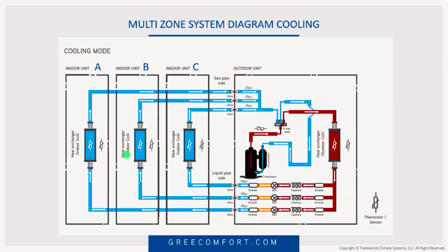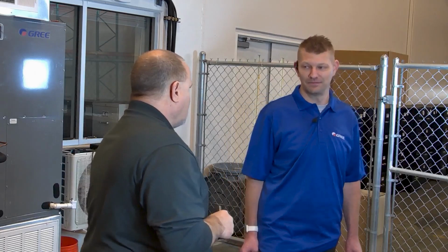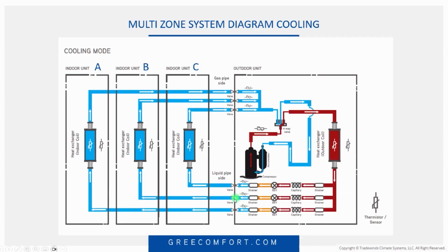So that's why we preach all day long to you guys, when you call in, you've got to unplug those thermistors. They're marked on the wiring diagram of the unit, and take an ohm reading of those thermistors. And what I preach all the time, JD, maybe you've got a different thought process, I tell them, look, leave the thing off for 30 minutes. Yep. Look for the odd man out. Even if you don't have a chart, if I'm checking all of the liquid and gas thermistors, and I ohm this one out and it's 20K ohms, and this one is 20K ohms, and this one all of a sudden is 5. You know you have a bad one. I just found the bad one, right?